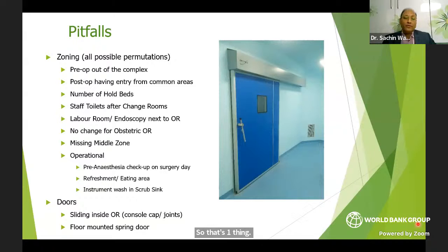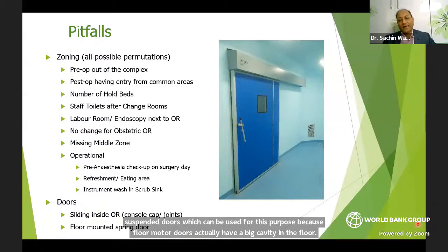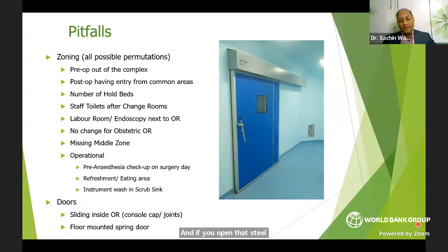Also, a lot of people use floor-mounted spring doors to swing the door both inside and outside the OT. Nowadays you have ceiling-suspended doors which can be used for this purpose, because floor-mounted doors actually have a big cavity in the floor, and if you open that steel cap, you'll find a lot of dirt filled with junk in that. That is again one area where contamination should be avoided.